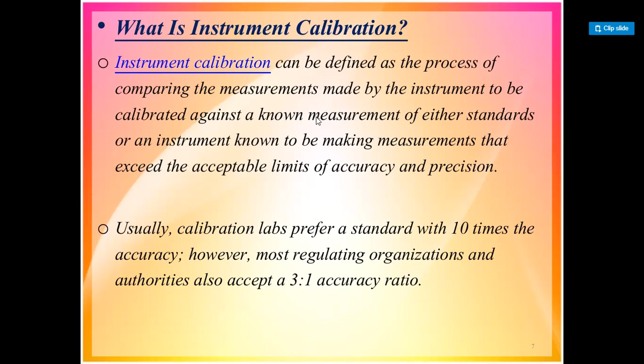So how will you calibrate, or make those measurements precise? First of all, the readings given by our test equipment are compared with our standard or reference equipment, so that we can get a standard limit and rectify the changes shown by our sample equipment. Usually calibration labs prefer a standard with 10 times the accuracy. However, most regulating organizations and authorities also accept a 3:1 accuracy ratio.